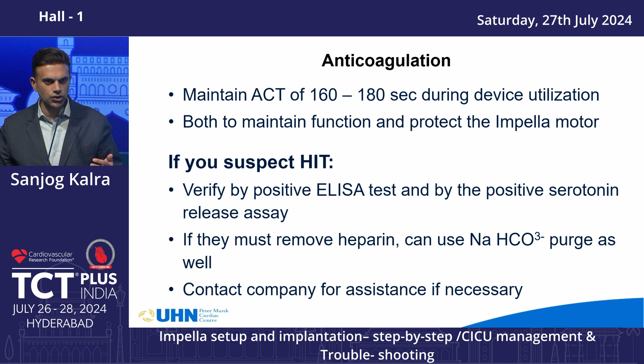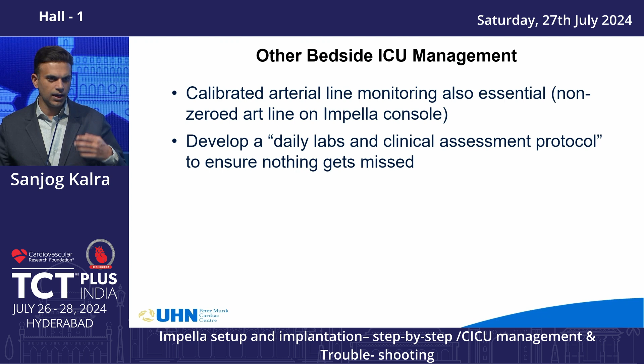And then other important pieces are making sure that you have a calibrated art line, because the placement signal, though it gives you a blood pressure, is useful. It is a non-zeroed art line. And then develop a daily protocol to supervise the device when it's in the unit. Every day you do an echo, every day you get hemolysis labs, every day you check the position, both on the device at the leg as well as within the heart.